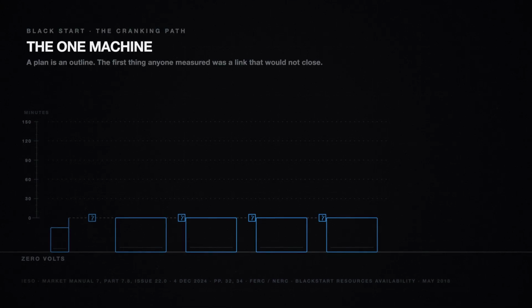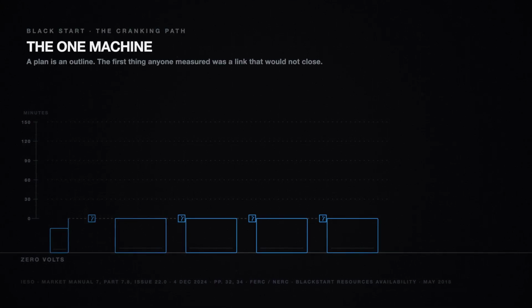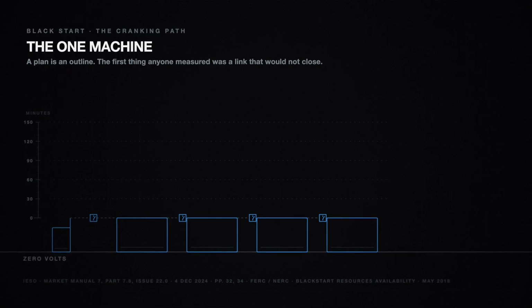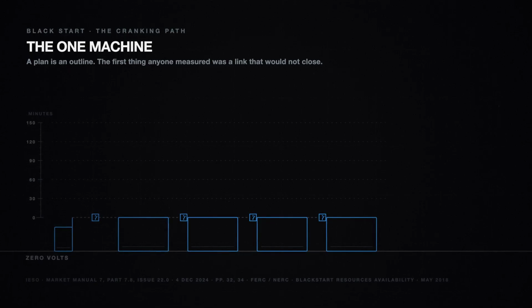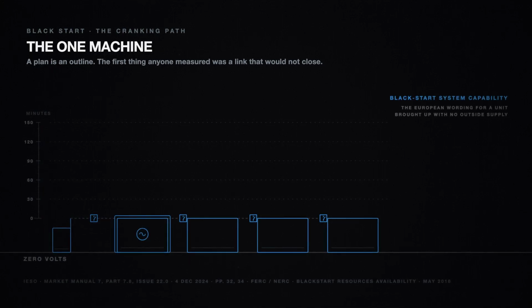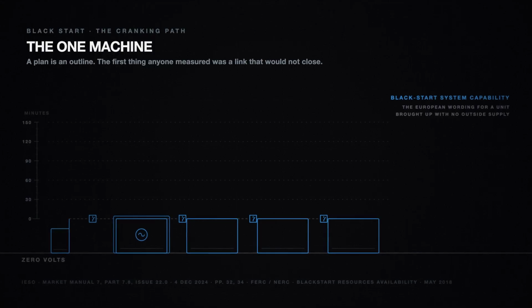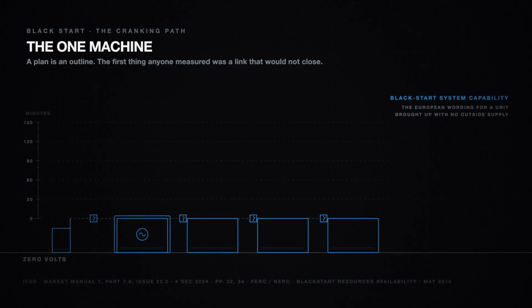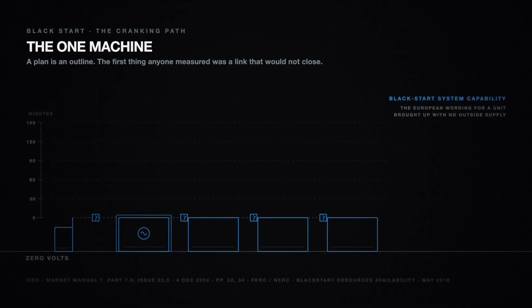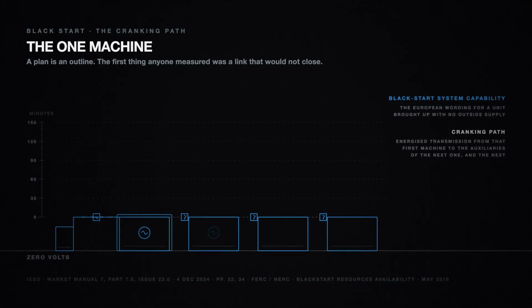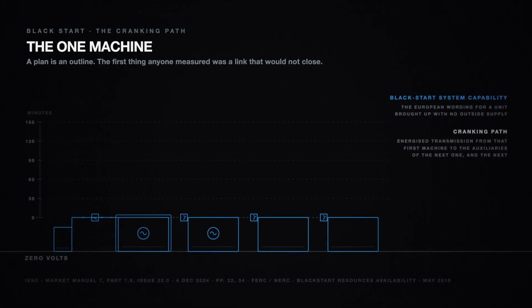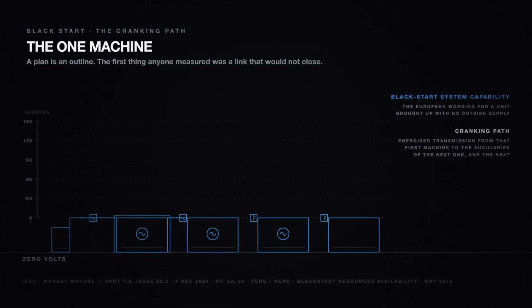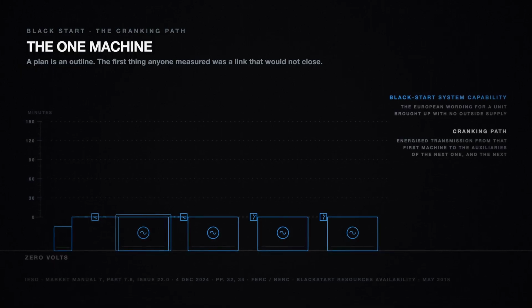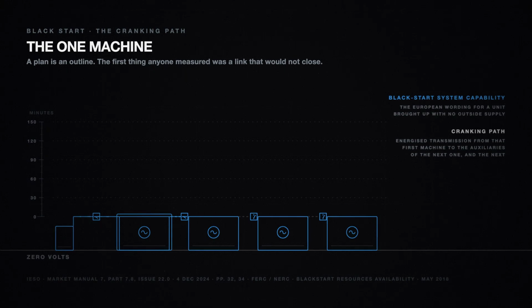A black start is the procedure for restarting a power system that has completely died. No voltage anywhere on it, and no outside supply to draw on. It begins with a unit that can be brought up without one, a plant with, in the European wording, black start system capability. From there, the plan works outward along what the industry calls a cranking path. Energized transmission from that first machine to the auxiliaries of the next one, and the next, until enough of the system is alive to be joined together.